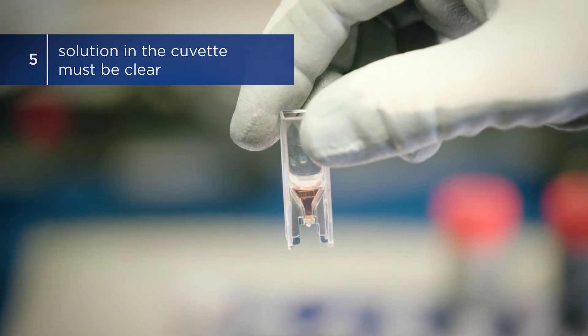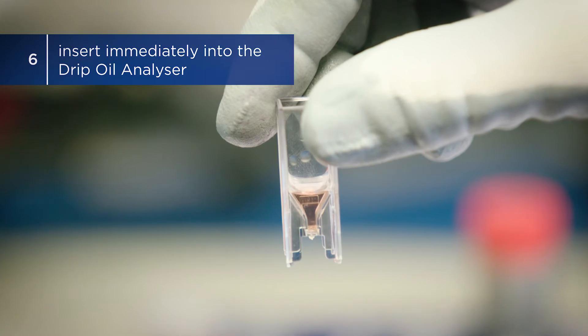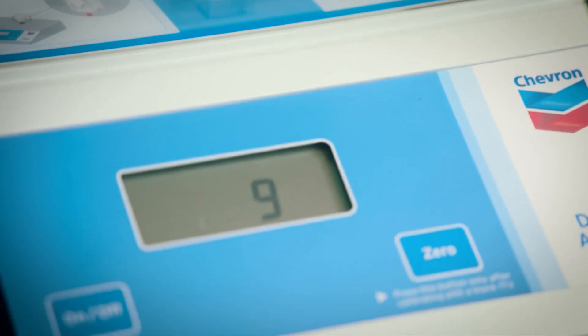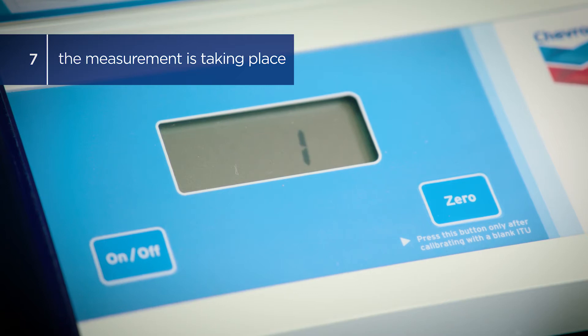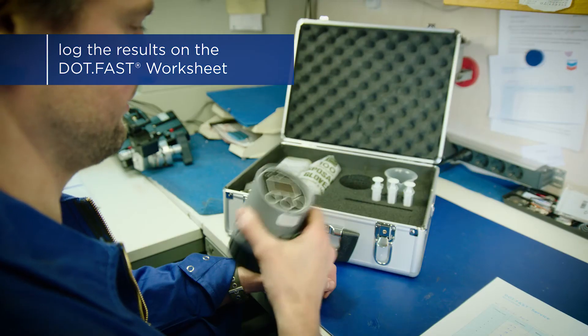Step 5: Proceed only when the solution in the cuvette is clear. Step 6: Since the chemicals contain solvents and water, the solution in the cuvette can evaporate and alter the readings. Therefore, immediately insert the cuvette into the drip oil analyzer as shown on the instruction label. Step 7: The display will count down while the measurement is taking place. The final reading will be shown in ppm. Read the display result and record it on the DOTFAST worksheet. If the iron level is above 2000 ppm, the display result will read plus 1999. To complete the batch, repeat all previous steps. It is recommended to analyze the residual total base number on each sample by using an onboard BN test kit. Also log these results on the DOTFAST worksheet.